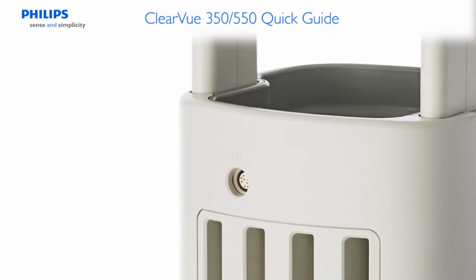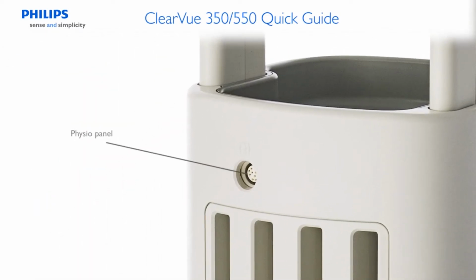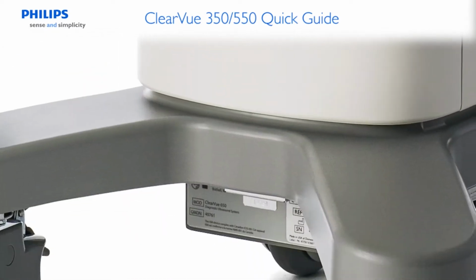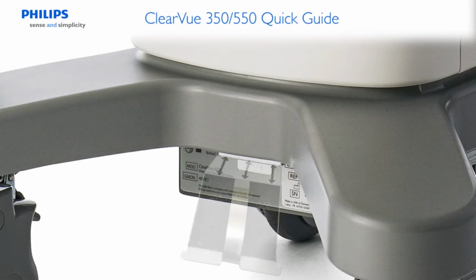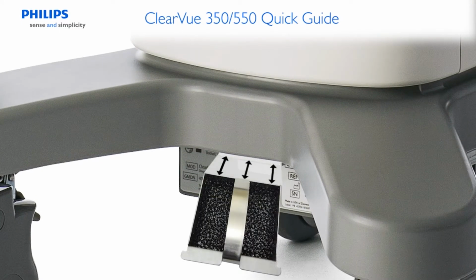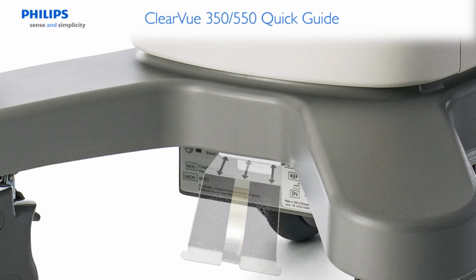The Physio panel supports standard ECG connection. The air filter is located underneath the system and pulls out for cleaning. It is important to clean the system filter to ensure adequate cooling of the system components.